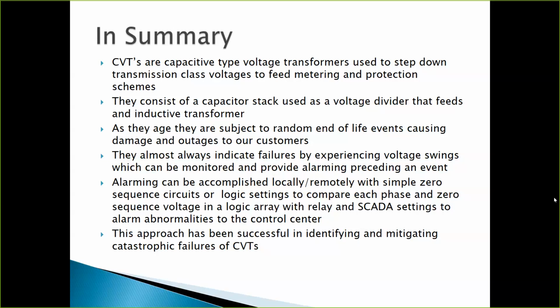It's the fact that they've been in service for 20 years and they've been exposed to every transient on the system over that time, and they degrade. And so that's the problem we have. But accuracy for us is not an issue. But we do alarm for that. But for the new style Trench and other manufacturers, they use a different paper in there on the capacitor stack, so they're much better.